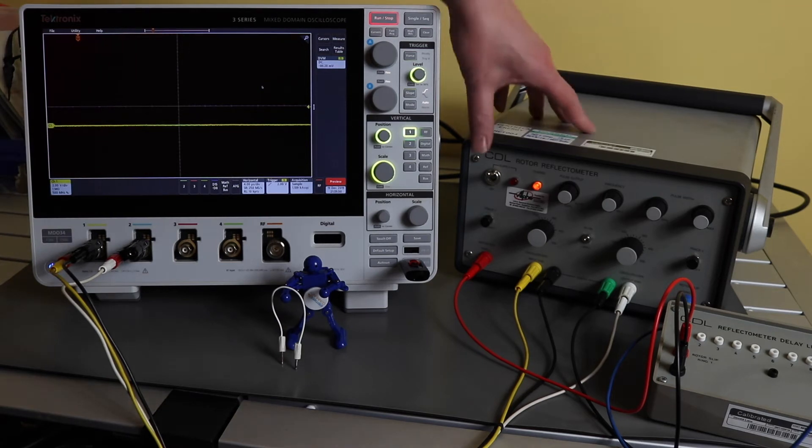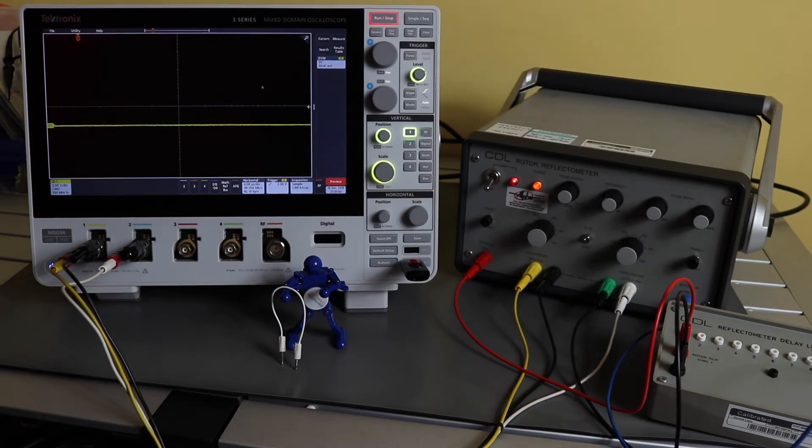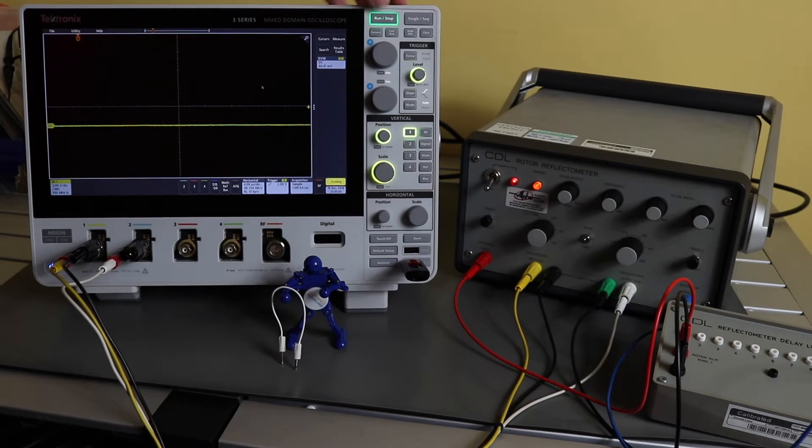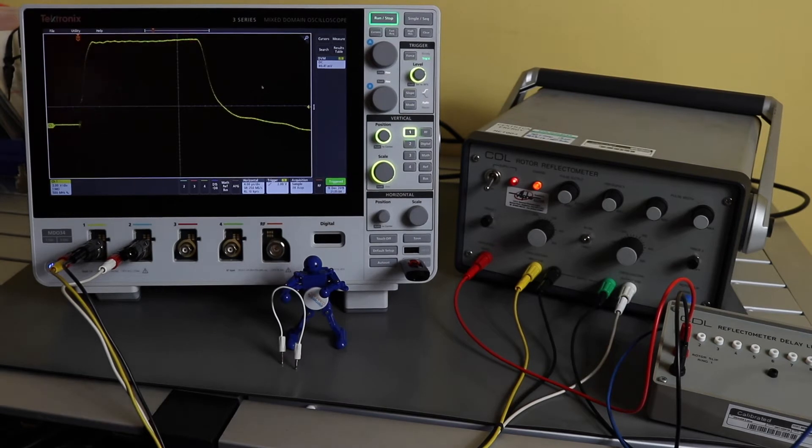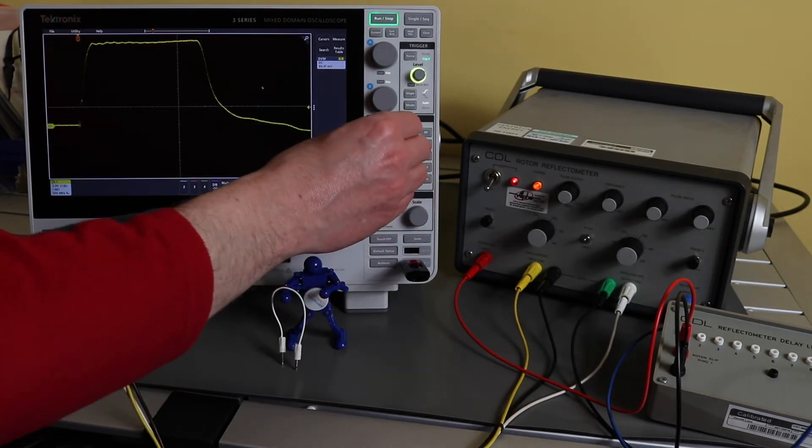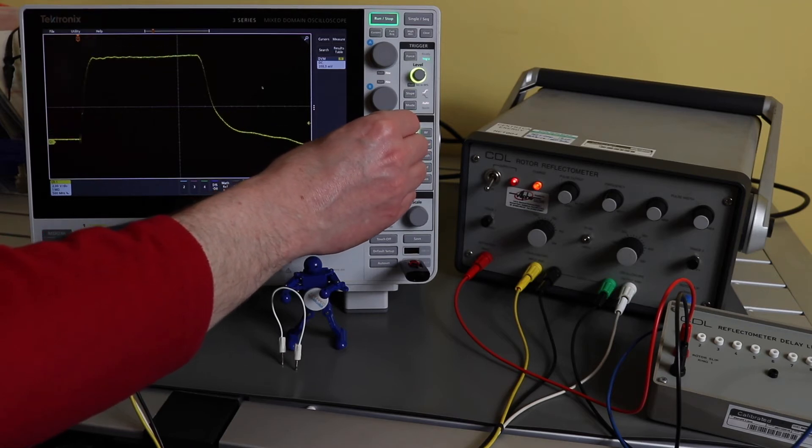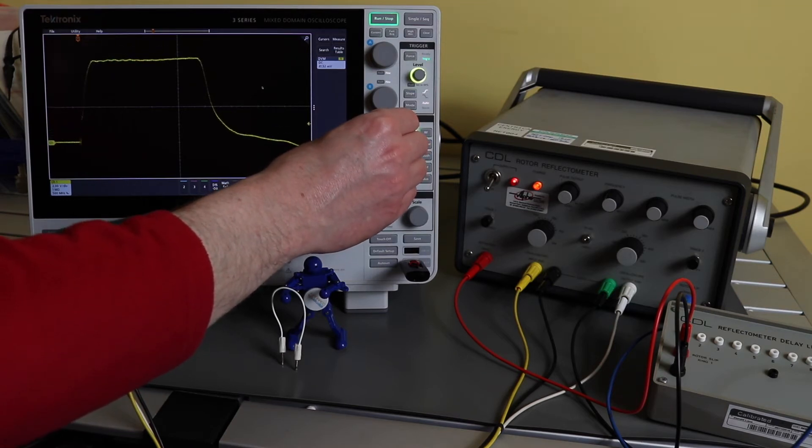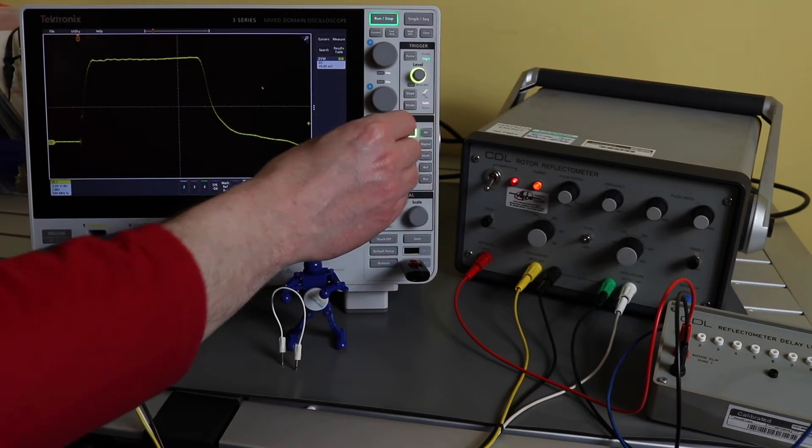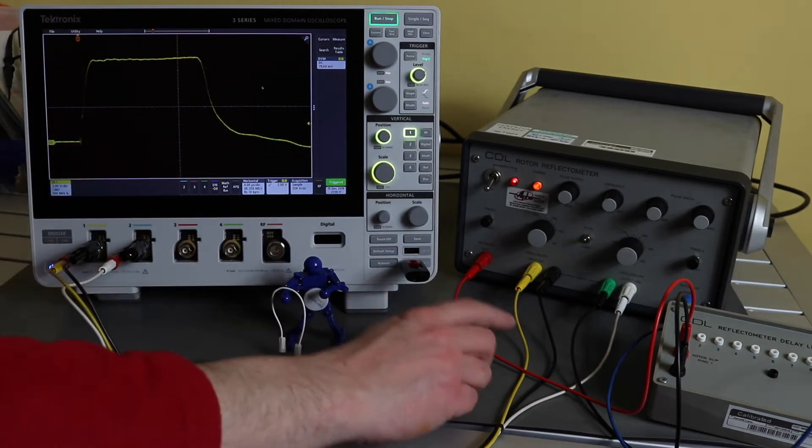So we'll turn on the reflectometer, start the scope up, and there's the double transit trace. Just bring him down a little bit. So that's both traces being in there.